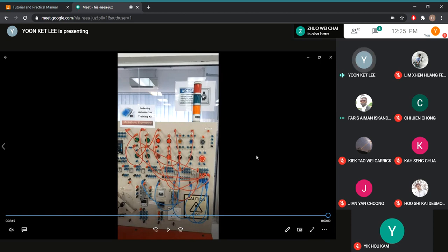You get what I mean? So there are 2 different types. If I use the retentive timer, I have 2 seconds, 2 seconds, 1 second, then I will hit my preset value. If I use the on delay timer, 2 seconds, 2 seconds, and the other day 2 seconds, then nothing will happen because they never hit the preset value.